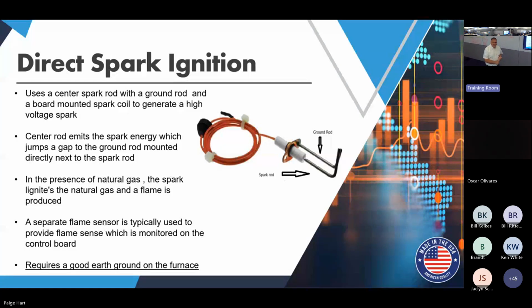A lot of the older houses, like before 1950, many times didn't run an earth ground. They used the neutral as the ground in the house. That could be a real problem when you're using direct spark ignition. You have to have a good earth ground, which means there's a rod driven in the ground that creates an earth ground that's part of your main electrical box. So this uses a center spark rod with a ground rod and a board-mounted spark coil to generate a high voltage spark. That spark lights a flame, or lights a gas that's under pressure.